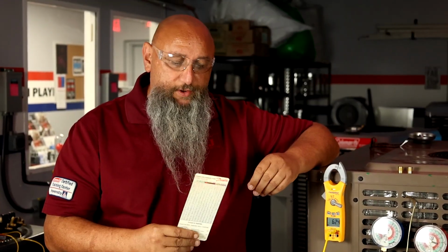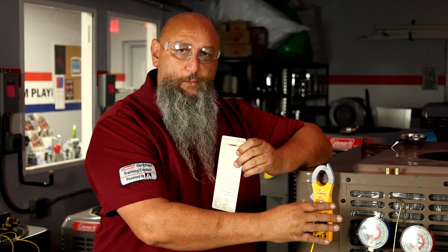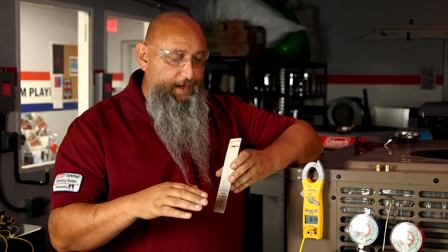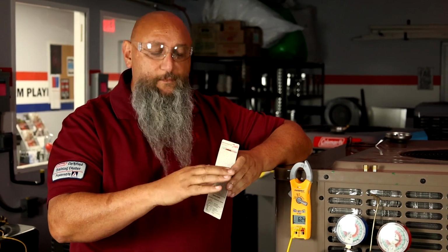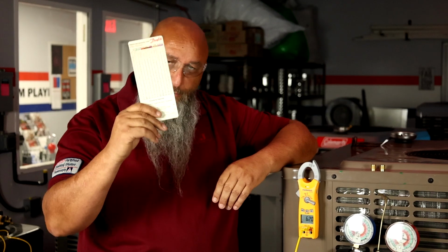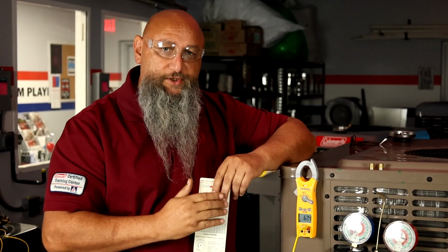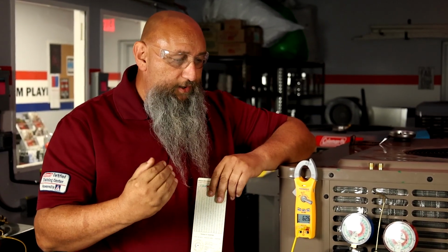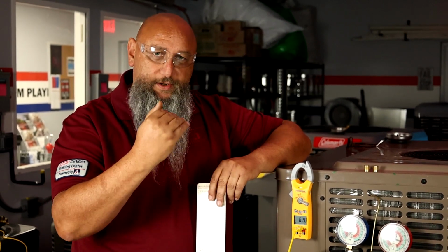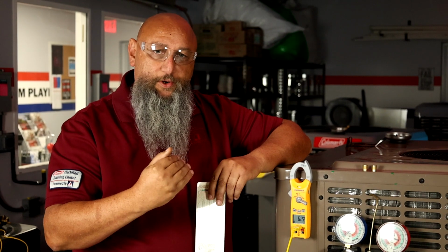Okay, so just to recap and maybe even offer a different explanation, when we take a pressure reading on our low side, that pressure is convertible to a temperature based on our temperature-pressure relationship, or one of these cards, or on the gauge itself. It's important to understand that that's a constant. That's our saturation temperature based on our pressure, right?